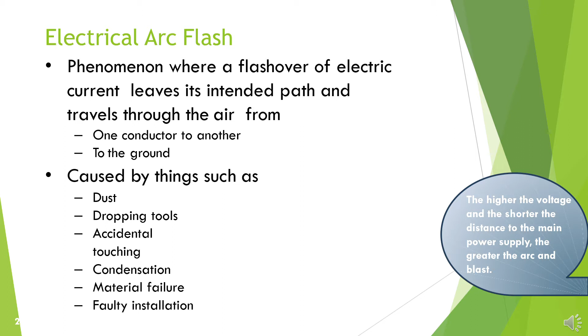Injuries from an electrical arc flash can be very severe. In fact, they could result in a fatality. So it's important that we're looking at the factors that affect the severity of how bad an injury can actually be from an arc flash. When we're trying to protect against it, we need to establish what proximity the worker is going to be from the actual arc flash hazard that potentially might be present. So this is why we're going to talk about boundary distances away from any type of potential arc flash or energized circuits. Then we're going to look at temperature.